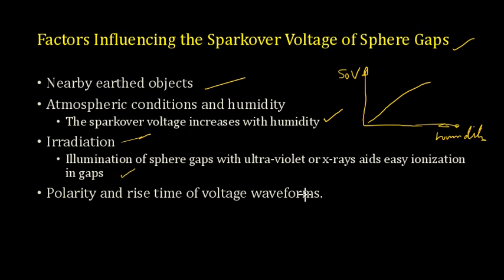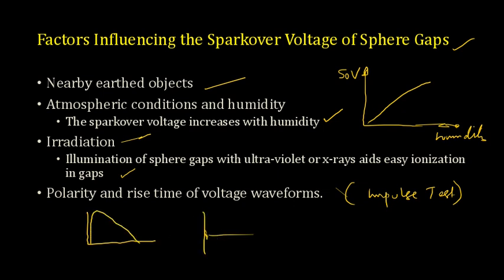And polarity and rise time of voltage waveforms also affect the spark over voltage. If you are having two polarities, a positive polarity waveform and a negative polarity waveform, especially during impulse tests where your polarity is being defined, you can have an impulse like this, you can have an impulse like this. So these are two polarity impulse waveforms. Depending on the polarities also, the spark over voltage is seen to be different, as well as the rise time of the voltage waveform. Rise time is simply the time required by the waveform to start from 0 and reach a particular value.